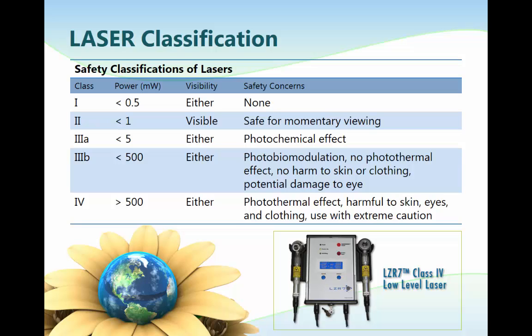Class 2 lasers have a power of less than 1 milliwatt. The beams are visible and these are considered low power lasers with visible light emission. The normal eye blink reflex, approximately 0.25 seconds, will protect the eye from direct contact with the laser output. These lasers must be labeled with caution: 'Laser Radiation — Do not stare into beam.' There is also a Class 2A which produces visible laser output, such as those used in barcode scanners.